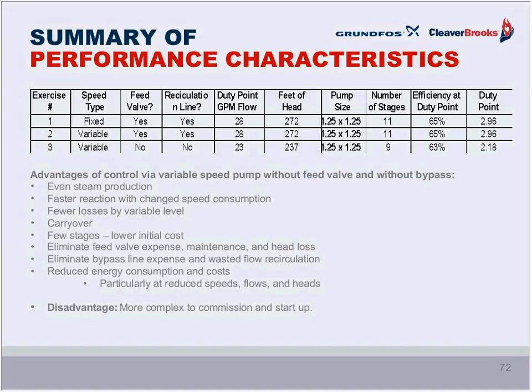The one from last month, number 2, was an abbreviated selection we did today, and then number 3 is the one we went a little bit deeper into. You can see which ones are fixed and variable speed, which take feed valves and recirc lines. And note how the flow and the head are lower for that variable speed controlled pump when the feed valve and the recirc line are not required.